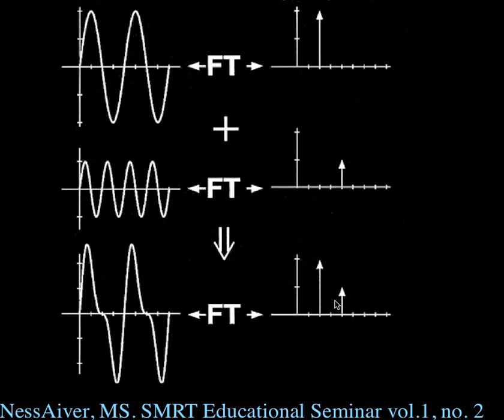So what we'll then do is, if we have, say, a 30 centimeter field of view, we'll put in a gradient on the field, and let's say we want a bandwidth of 15 kilohertz. Then we'll select a gradient in that direction so that negative 7.5 kilohertz will be all the way on the left side, plus 7.5 kilohertz above the center frequency will be signals on the right side, and we'll receive a signal bandwidth that is 15 kilohertz in width.